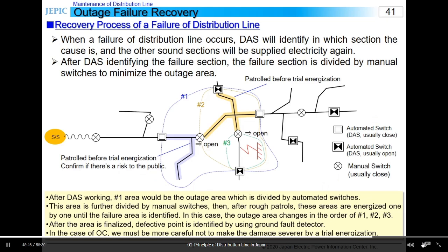The example is that a ground fault occurs in the third area. The first area, surrounded by blue, would be the outage area after the distribution automation system has identified it. When recovery workers arrive, they patrol roughly to energize again while dividing the section by manual switches. The areas divided by manual switches are tried to be energized one by one. The light blue line would be the first section where trial energization is done, so they first do a rough patrol on this line. A rough patrol is a patrol to confirm there isn't any risk to the public, such as an electric shock, line disconnection or something like that, and it's done as quickly as possible.